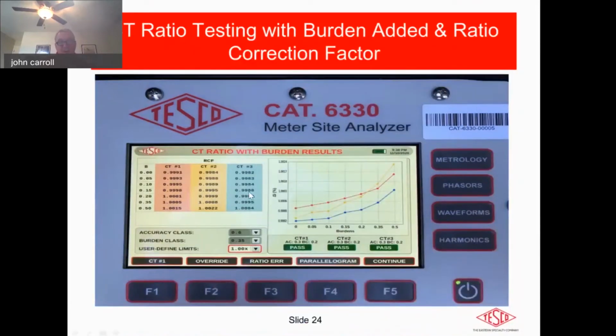This one is another one I just showed to give you an idea of what else we can do, which is a ratio correction factor, which is something that's also usually on the nameplate. And this is just giving you the ability to put in a correction if it's necessary. In most cases, even with 0 burden, you can see it's almost 1. But you do get variations, which is why we do these tests.